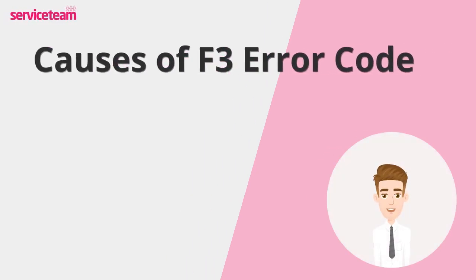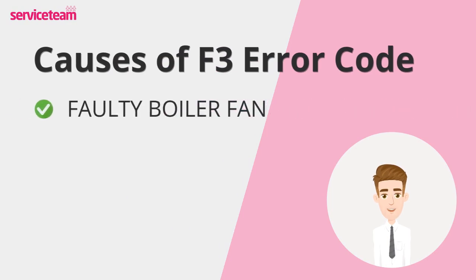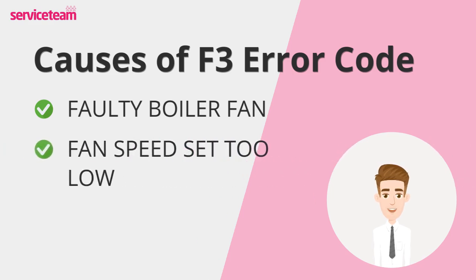Let's see what causes the F3 Ideal error code. A faulty boiler fan can directly cause the F3 fault code — wear and tear over time can lead to fan failure, making replacement necessary. When the boiler's fan speed is too low, it won't effectively push out these gases, triggering the Ideal F3 fault. This can happen if the fan wasn't adjusted properly during installation, or if the fan components have worn down over time.